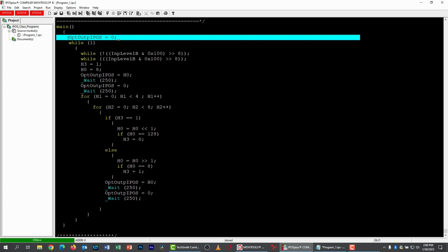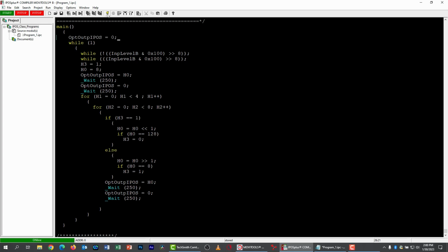So what I'm going to do now is click the lightning bolt here, which will start task number 1, start the mystery program running. So I will click the lightning bolt, and you notice that the first p-stop changed from red to green, and now it says start. That means task number 1 is running. Now looking at my control box, nothing is happening at the moment. But remember, I told you you had to switch DI10 from off to on to off again. Now I have all my switches in the off position at the moment, so I'm going to go ahead and flip that switch and see what happens, and I'm going to turn on the camera so you can see what happens. So here we go.